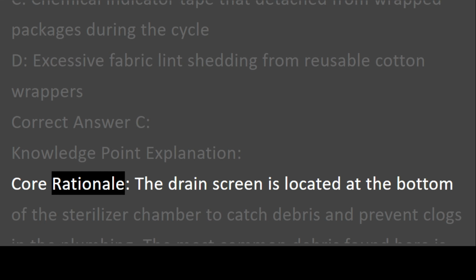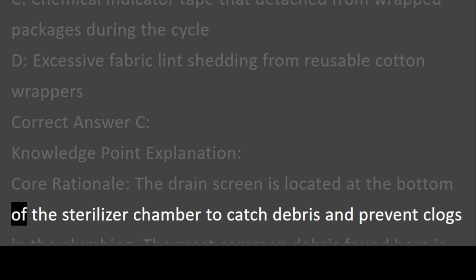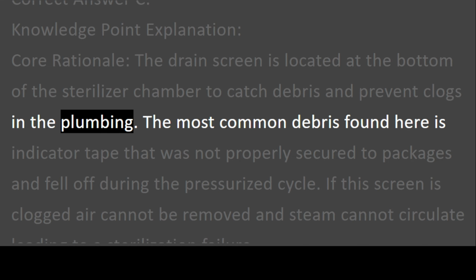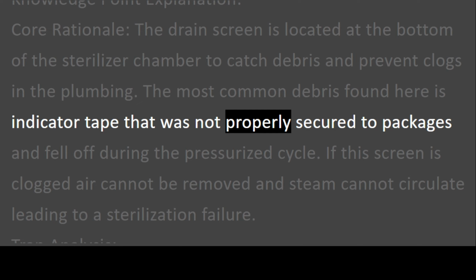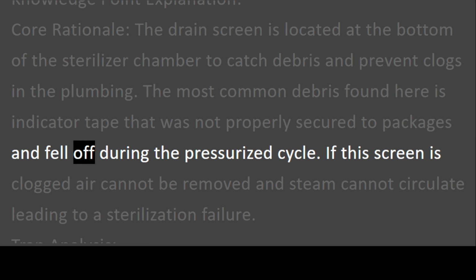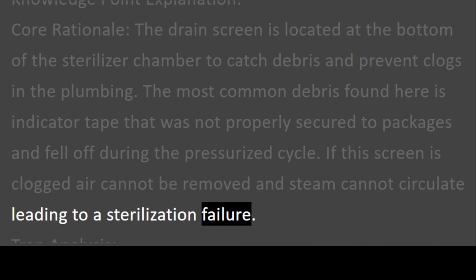Core rationale. The drain screen is located at the bottom of the sterilizer chamber to catch debris and prevent clogs in the plumbing. The most common debris found here is indicator tape that was not properly secured to packages and fell off during the pressurized cycle. If this screen is clogged, air cannot be removed and steam cannot circulate, leading to a sterilization failure.